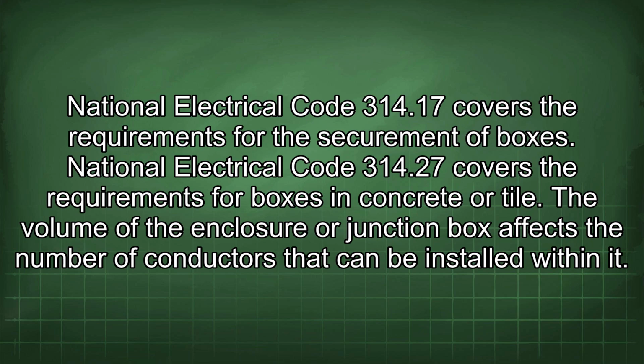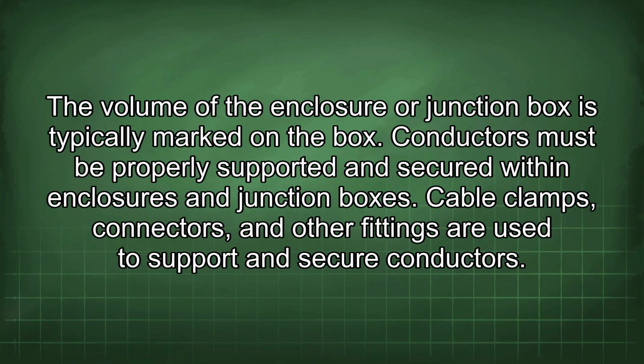National Electrical Code 314.17 covers the requirements for the securement of boxes. National Electrical Code 314.27 covers the requirements for boxes in concrete or tile. The volume of the enclosure or junction box affects the number of conductors that can be installed within it. The volume of the enclosure or junction box is typically marked on the box.